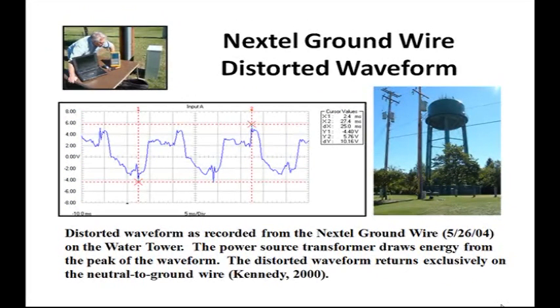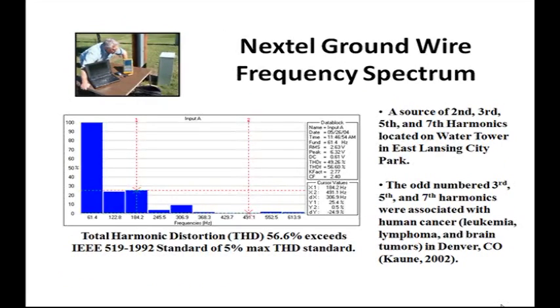Nonlinear loads, such as the Nextel electronic AC-DC converter, are noted for taking their energy from the peak of the waveform. The waveform we captured from Nextel's neutral wire is a classic example of a distorted waveform. Note that the peaks have been bitten off from the waveforms. The frequency spectrum of the Nextel waveform contains generous amounts of 180 Hz, 300 Hz, 420 Hz, 540 Hz, and other multiples of 60 Hz.